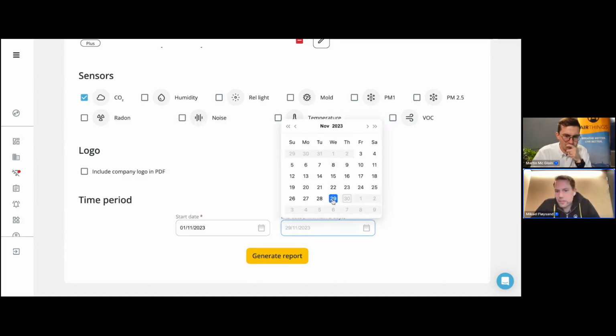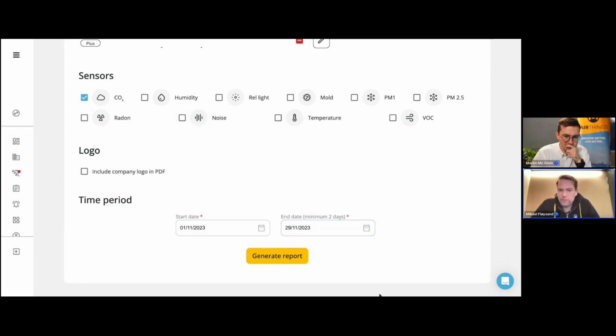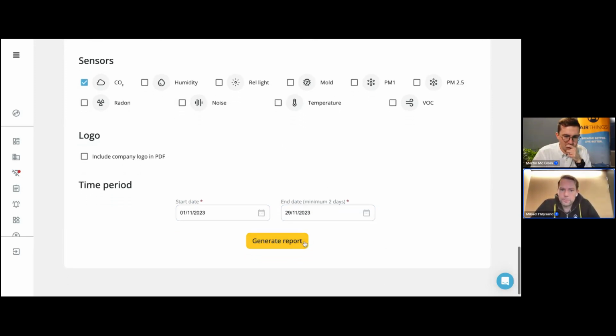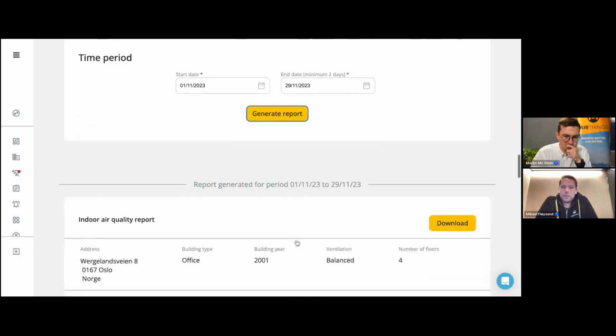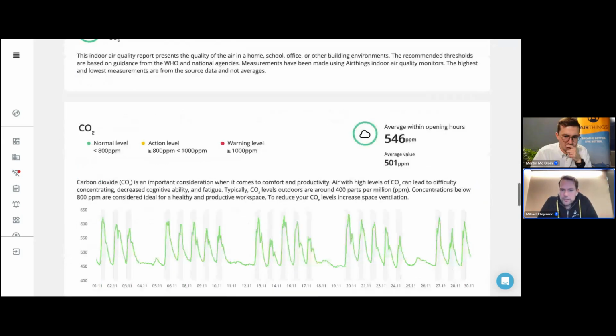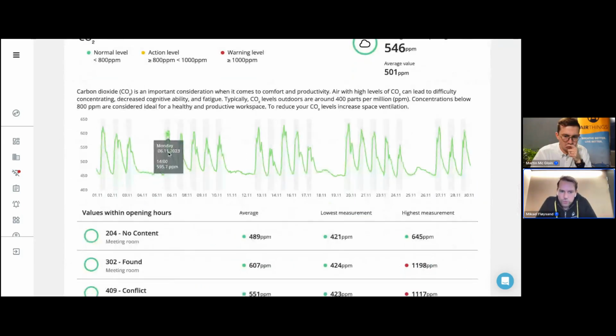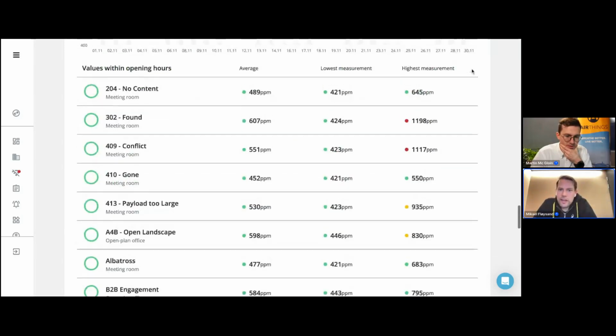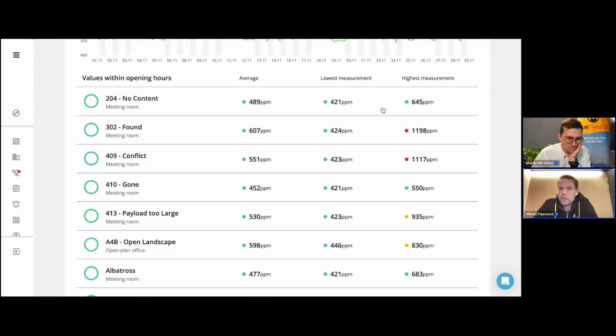This building isn't actually the best example because it has a demand-controlled system, but you see here it's the same kind of pulse: CO2 levels generally high when there's people in the building within opening hours. If you look at the building average as a whole, you also get averages, lowest and highest measurements within opening hours for each individual space, and this is where you actually want to be looking.